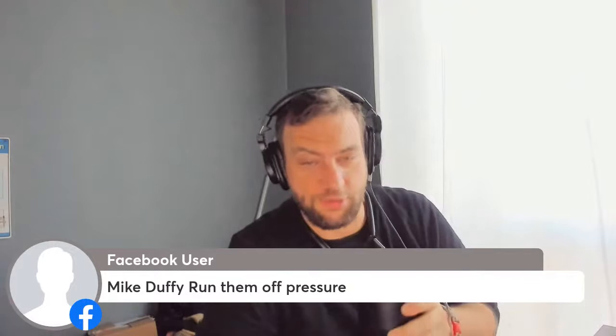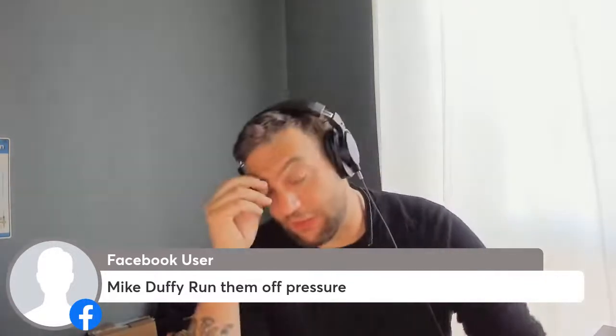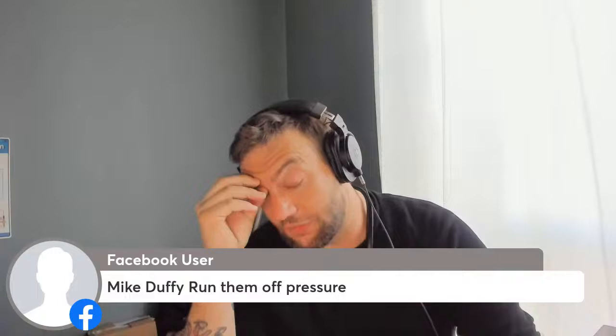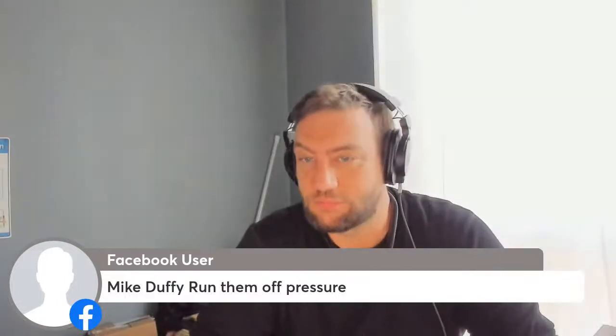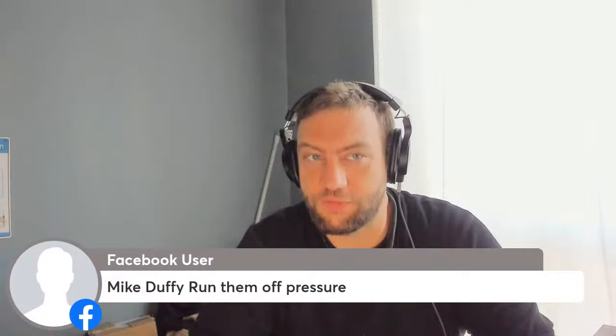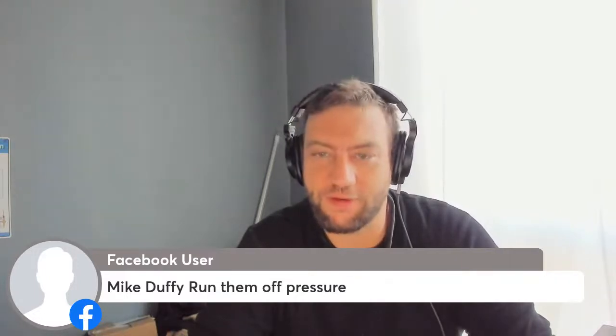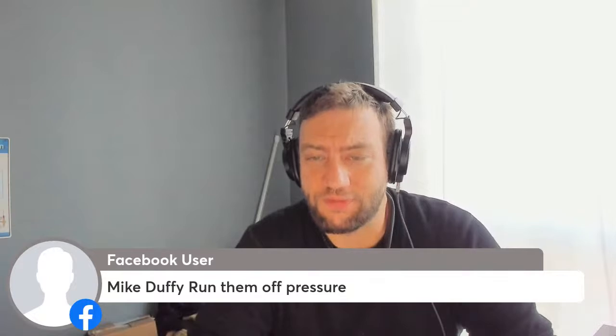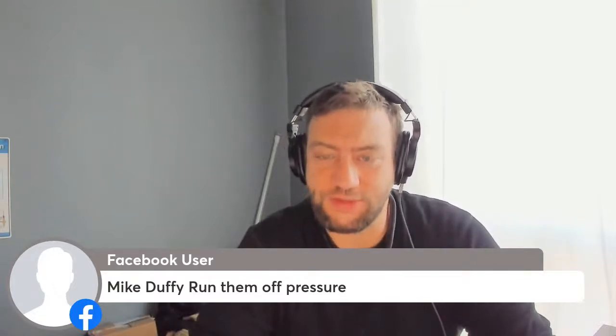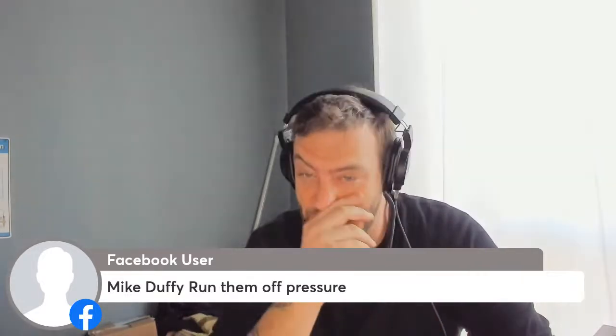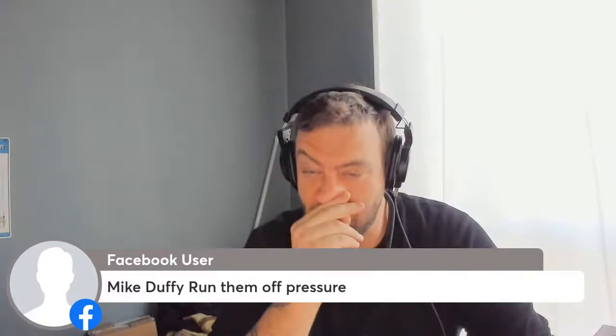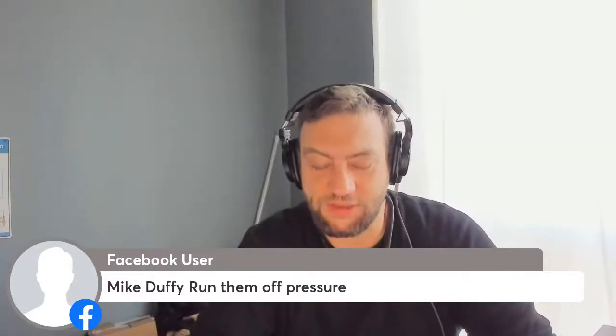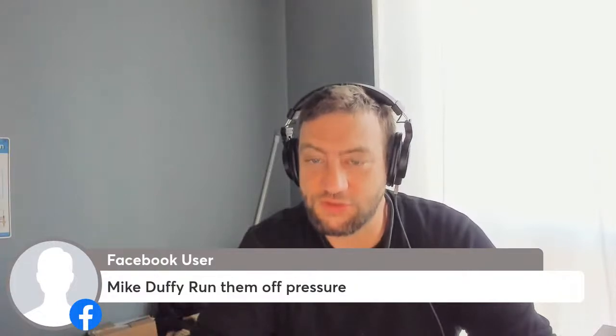Run them off pressure. Yeah, absolutely. But like I said, for E2, that would require you to run a loop sequencer, where it's basically acting like a mechanical EPR at that point. Typically all the CDS valves that are programmed out there are programmed to work off the temperature average of the cases. Where you're trying to maintain a specific pressure, you would need the input, the suction pressure of the pipe, and then try to make that CDS valve achieve that pressure.